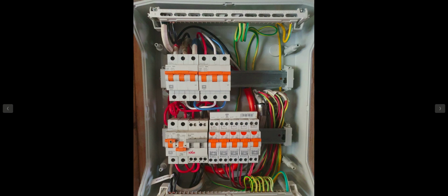But look here, we've got this main switch coming in. That's from the grid side. Another one next to it is from the backup side of the Solis inverter, and it goes through this double pole changeover switch, because if the Solis ever shits itself, all your backup circuits are going to be dead too. So you've got to have a double pole changeover switch, so you can switch the neutral as well from the backup output from the Solis back to the main switchboard.